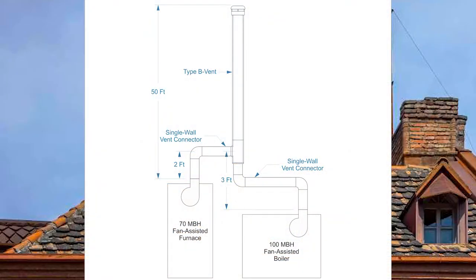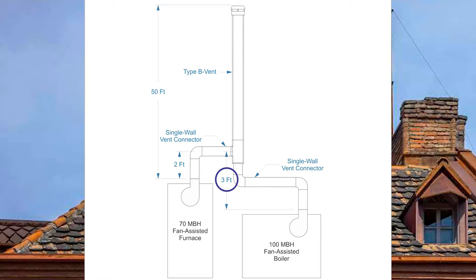For the next example I have two fan assisted appliances dumping into a 50-foot common vent. The first is a 70,000 BTU fan assisted furnace with a two-foot vent connector rise. The other is a fan assisted boiler at 100,000 BTUs with a three-foot vent connector rise. The appliances have single wall vent connectors, therefore we must use table C4.